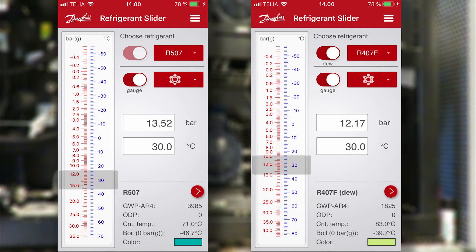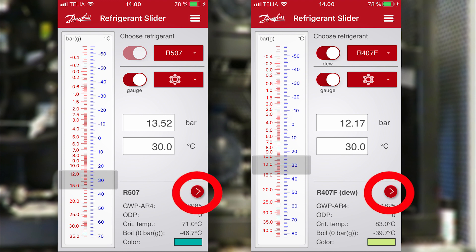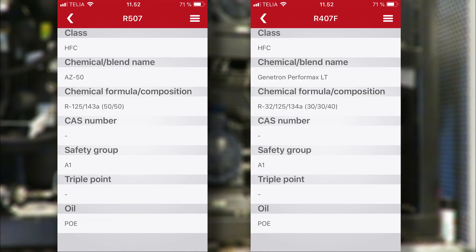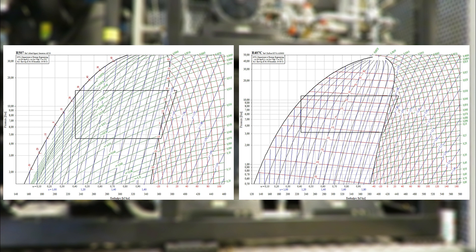To check a couple of other properties, you click on the right arrow to get the second page. If we look at the class, both are HFCs; safety groups are both A1, and finally both work with POE oil. Although you can get a fairly good picture of the refrigerant comparison with the refrigerant slider, there are quite a few more things to think of in case of retrofitting, so you should also consult the H-LogP diagrams to check enthalpy, among other things.